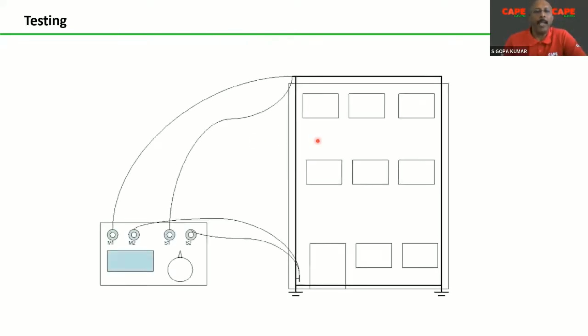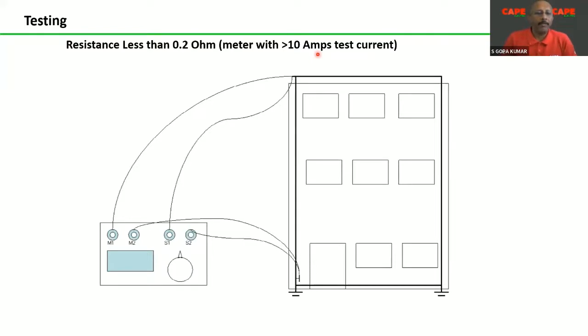Now, how is the performance of this natural component verified? It is carried out by making a continuity resistance test. I'm sure all of you are aware of the continuity resistance test. The important point is that you are supposed to make this test with a meter of minimum 10 amps current. I have seen in a lot of places the normal earth electrode testing meter used for this purpose.